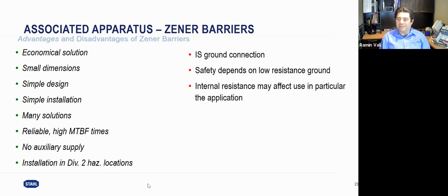Safety depends on the low resistance ground because the energy will be discharged through the Zener diode to the ground. So basically, we have to have a ground which can discharge the energy on it to create this protection. And because of this series resistor in the loop, we have a significant voltage drop. So that's another issue with the Zener barriers. We have to make sure that this voltage drop is not too high, so that we still get enough energy to power up our field instruments.